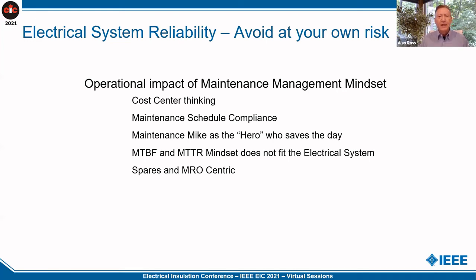We also have these maintenance terms, MTBF, mean time between failures, and MTTR, mean time to repair. These are two big maintenance and reliability acronyms, but they don't fit the electrical system. The mean time between failure of transformers, as I said, is 38 years, probably longer, but we just know it's 38 years. When your mean time between failure is 38 years, you're not thinking in terms of maintenance or reliability. You've completely lost it. And mean time to repair, well, that depends.